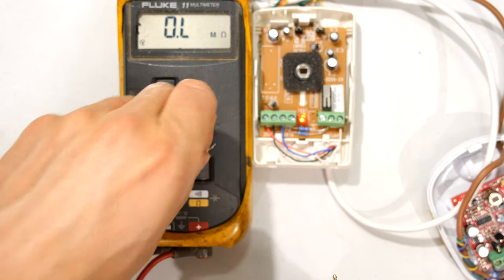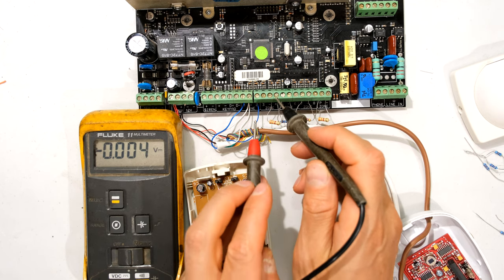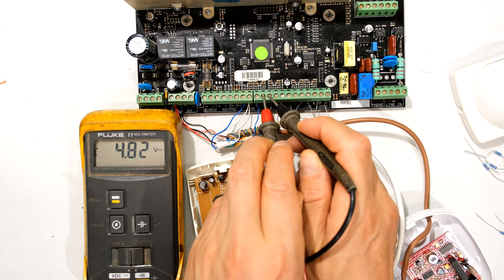Let me show you with the voltage. Look at the voltage of a zone that is currently open. There I've got zone 3. It is currently an open zone so it is measuring 4.82 volts. That tells me it's an open zone violated.